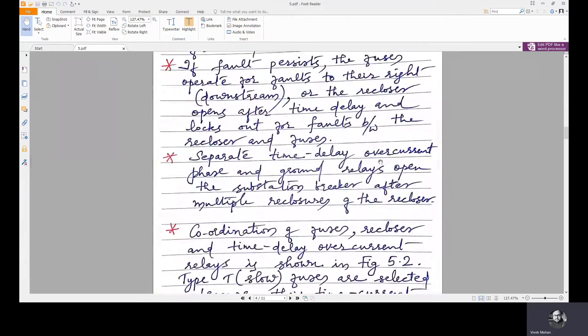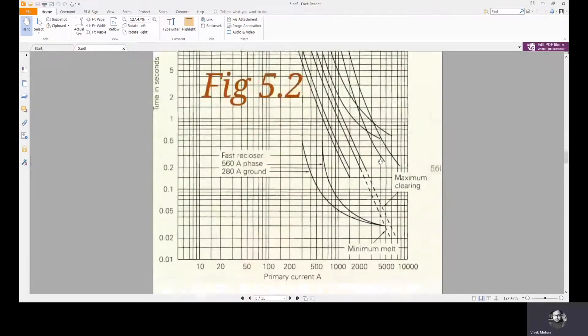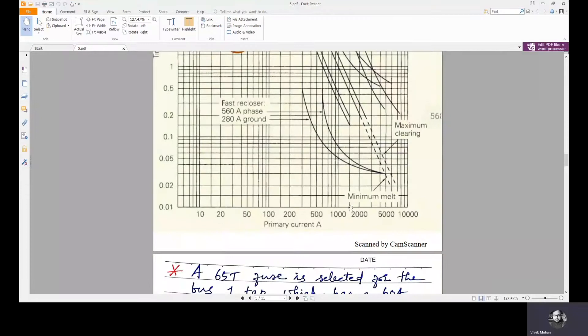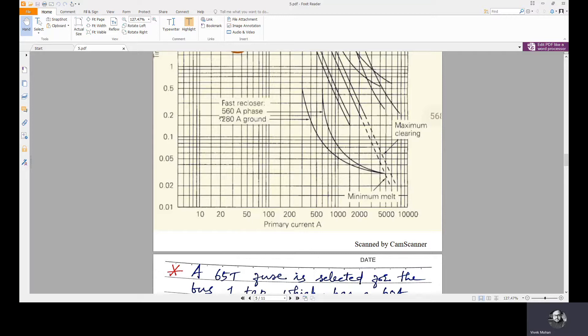We will go to the time-current curve where on the horizontal axis we take the point 1500 amps. For 1500 amps, the first event that would happen is the 280 amp ground, but that is not in the picture now. We have only the 560 amp phase fast recloser here, and this corresponds to 0.05 seconds. So at 0.05 seconds, the fast recloser will operate.